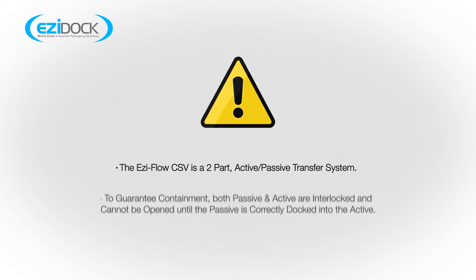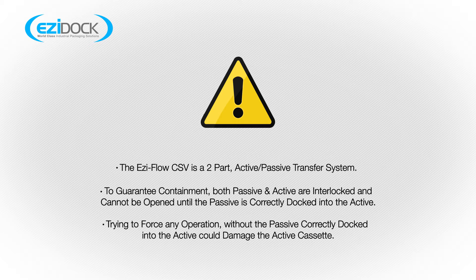It will help to remember these key points. The Ezi-Flow CSV is a two-part active passive transfer system. To guarantee containment, both passive and active are interlocked and cannot be opened until the passive is correctly docked into the active. Trying to force any operation without the passive correctly docked into the active could damage the active cassette.